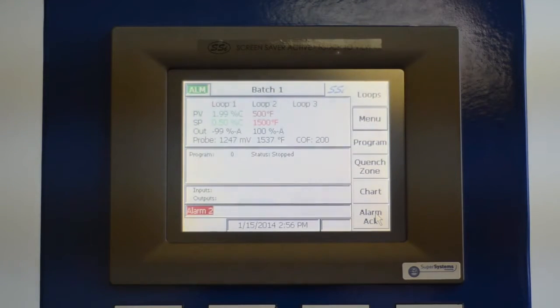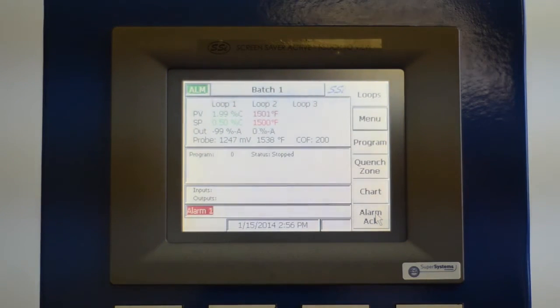So we'll go ahead and check the full range, take it up to 1,000. 1,500. And finally 2,000. And that's it. That would be calibrating the input number 3, terminals 27 and 28 on a 9000 instrument.